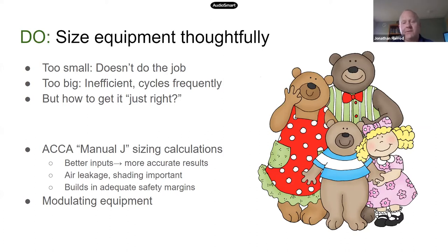That's one of the reasons that we like to, instead of just guessing what a house's air leakage is, actually go and measure it and spend the time to accurately put in the window shading, for example, the overhangs and things like that that will affect how much sunlight comes into a house on a hot day. So if we can do this calculation accurately, we're going to end up with a system that is correctly sized to the house.